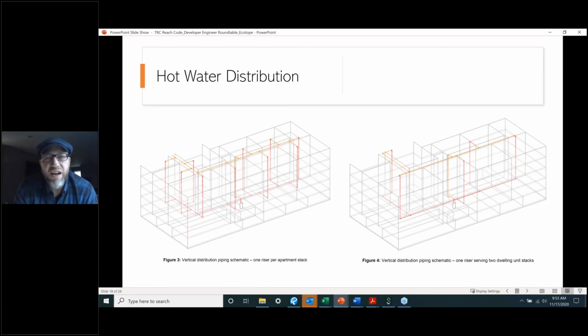There's a bunch of strategies to try to reduce this. One would be to locate your plants more central—versus at the end of a building, you want to be located more central because you can take your hot water pipe and go straight up. If you look at this schematic on the left, it splits left and right, and what that does is reduce the size of your pipe down there.